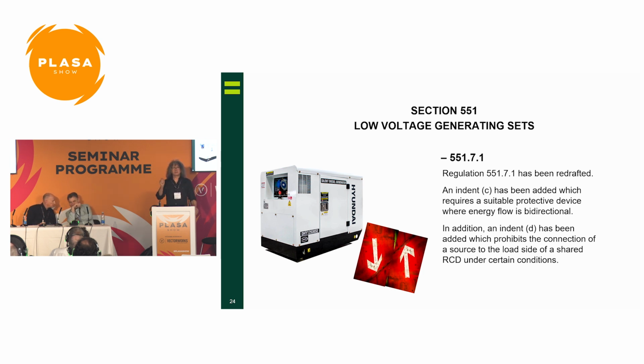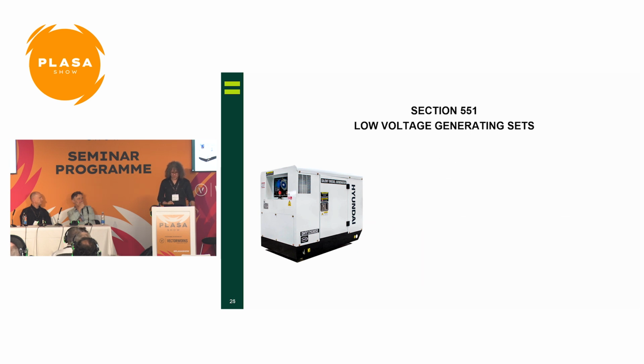It's all about the labeling - we've got the load and the supply end, conventionally that's what we see. Bidirectional devices either aren't identified, so you can connect any source on either side, or they've got markings to show they're bidirectional. It's important that where you've got multiple sources of supply, the devices you use are bidirectional - that's an important thing that's come along.